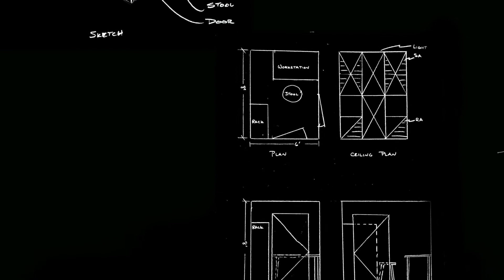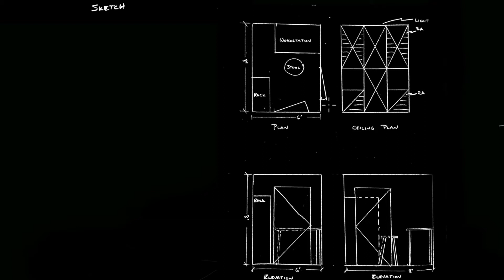Now the best way to look at this is from an elevation view, so let's move this up and sketch out some of the airflow. What we have here is the supply air, shown as X's with side dashes, supplying air to the space. Looking from this elevation, the cool air is coming down from the fan filter units, or the supply air filter units. And the way I've drawn the ceiling plan, the return air units, which we'll put in red, are over here, and that's the airflow going there.